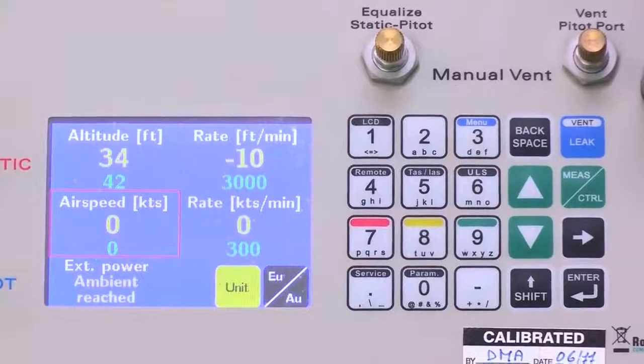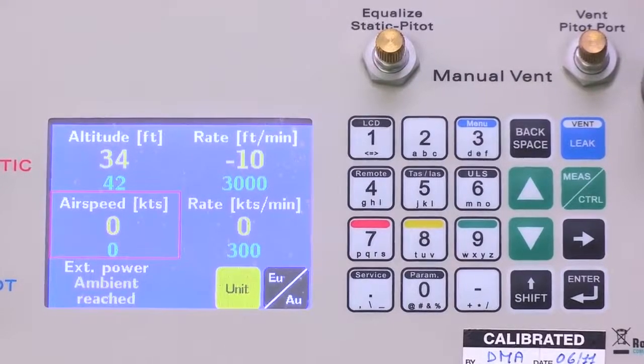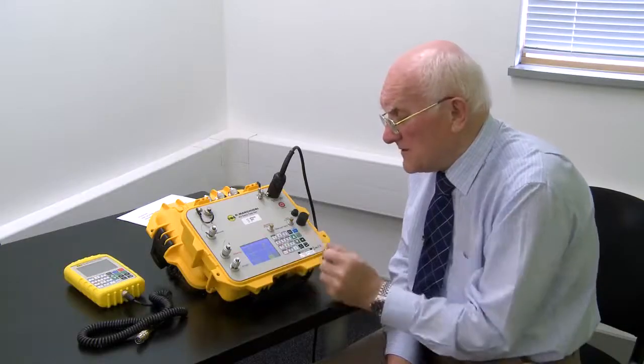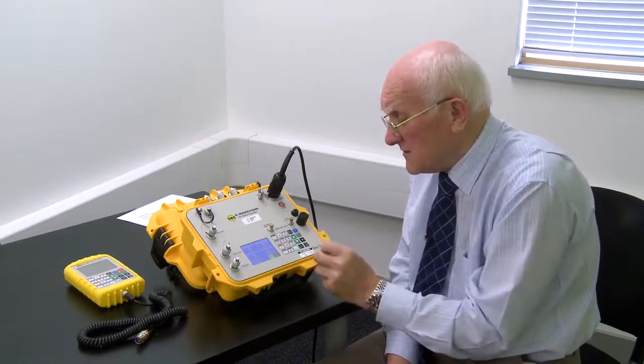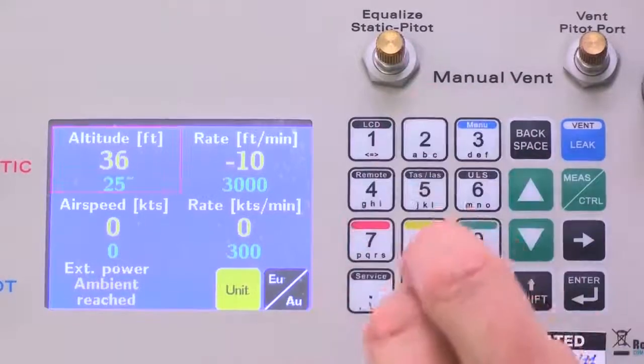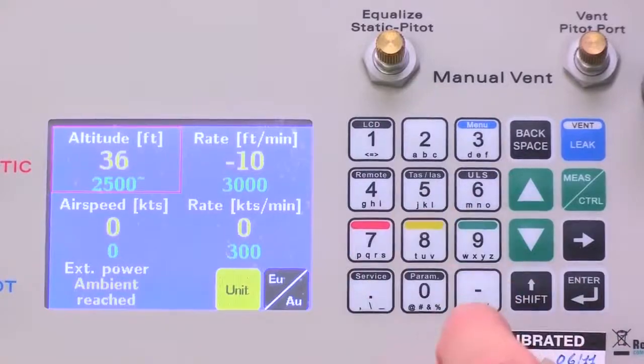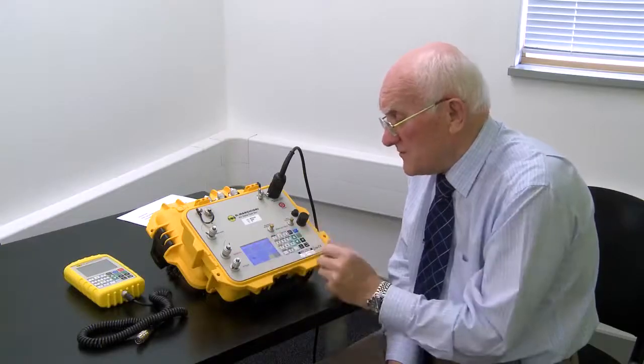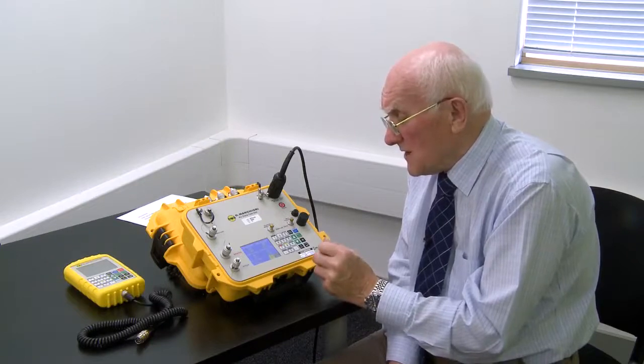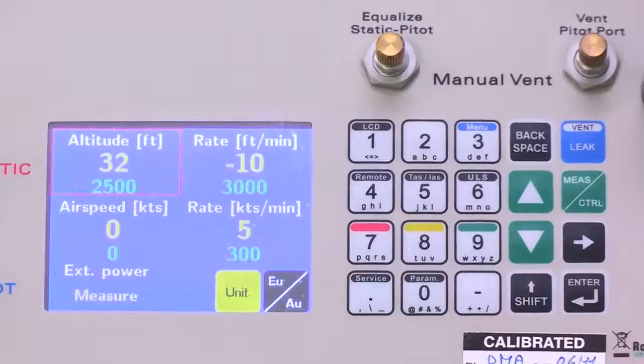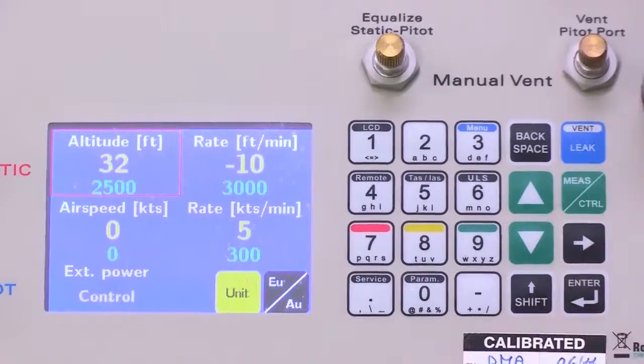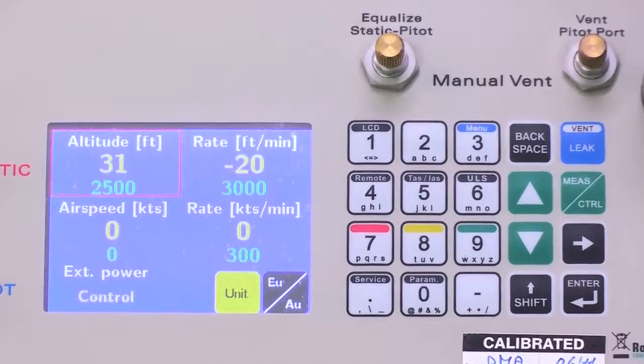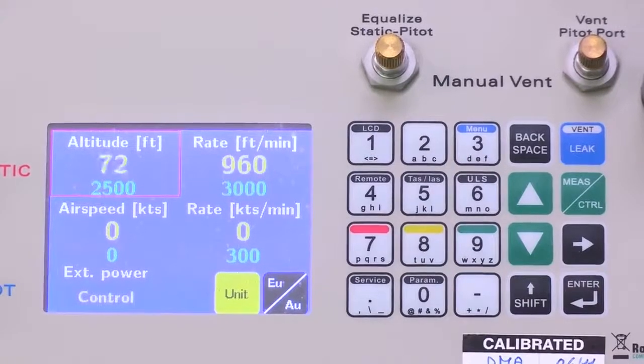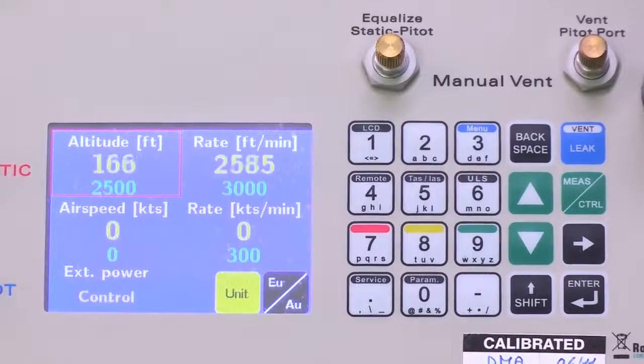Now we can start asking for pressures, putting in demand values for altitude - let's say 2500 feet. We've introduced that new demand value. We enter it with the enter key, go from measure to control, and we'll now begin approaching that value at the rate we requested, 3,000 feet per minute.